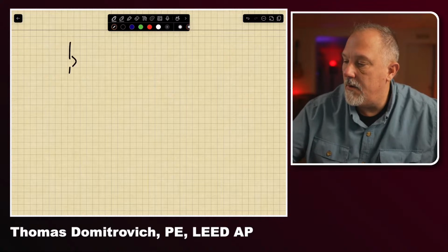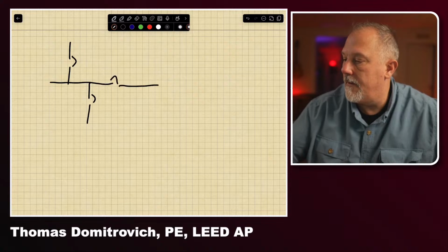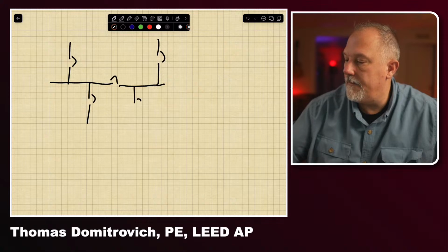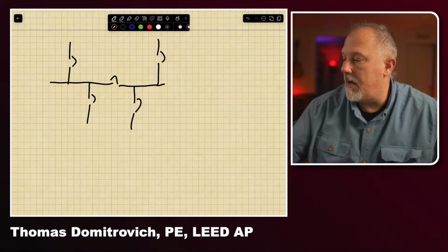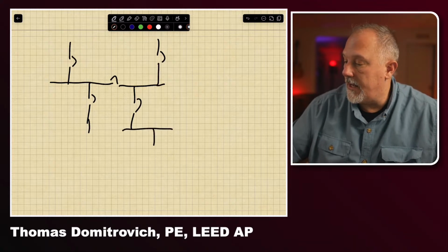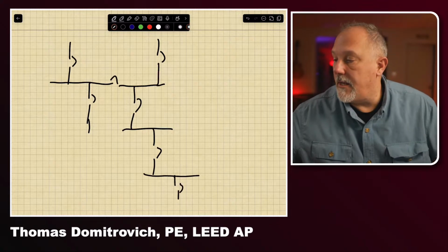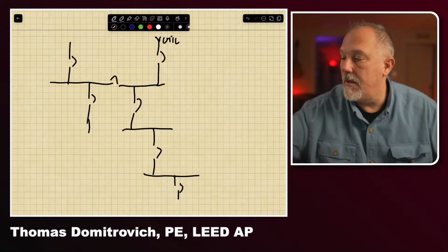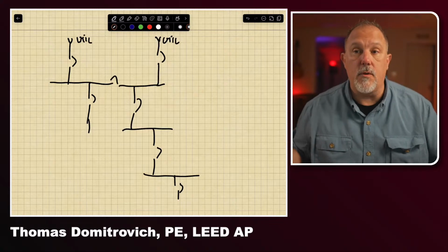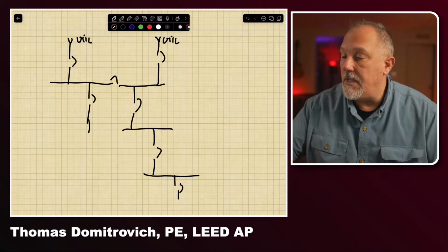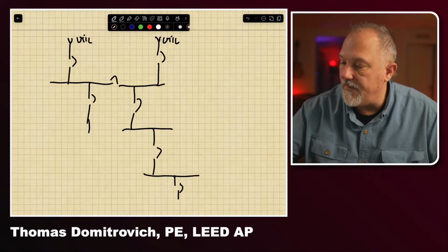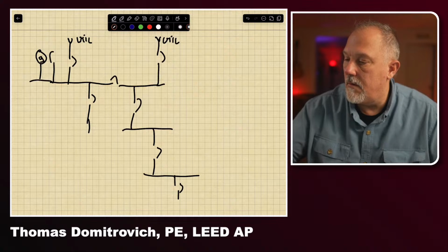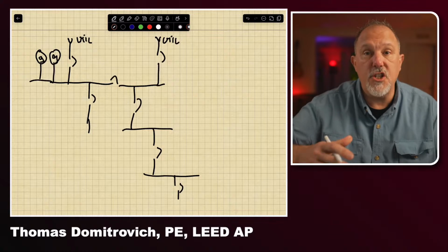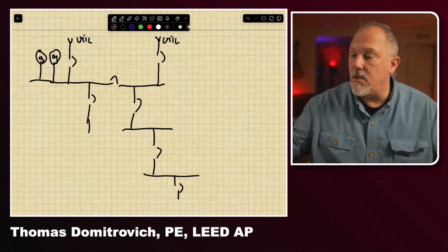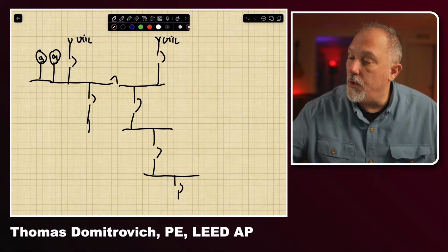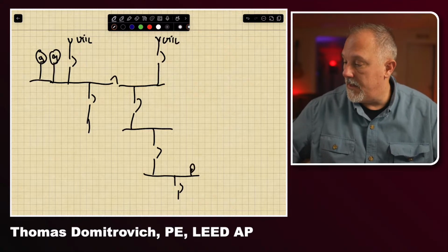If I had something like this going on, okay, and let's say I had a double-ended switchgear, and I had all of these things going on, and I had a utility here and a utility here. I'd say this is complex. I'm doing a main-tie-main configuration. Let's say, for example, I've got local generation connected to that bus, and the generation runs in parallel with the utility. I would need to run through the different scenarios. I'd have to say, which scenario gives me the most fault current at this panel 1?